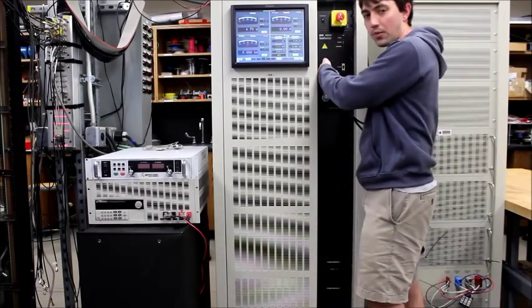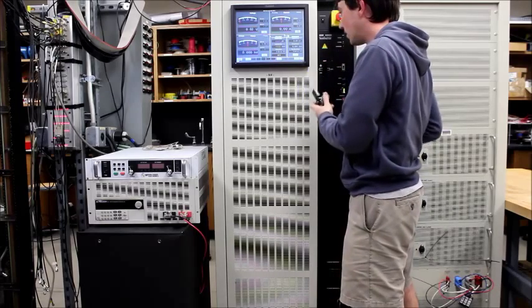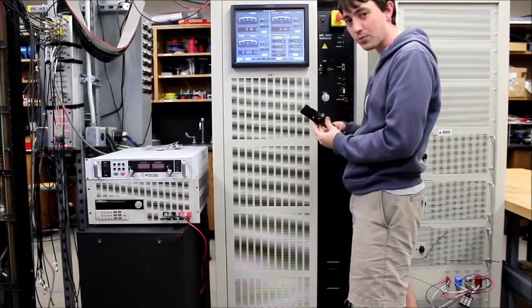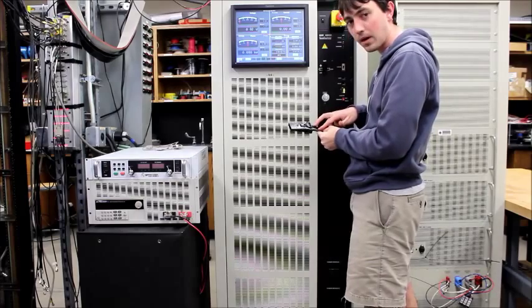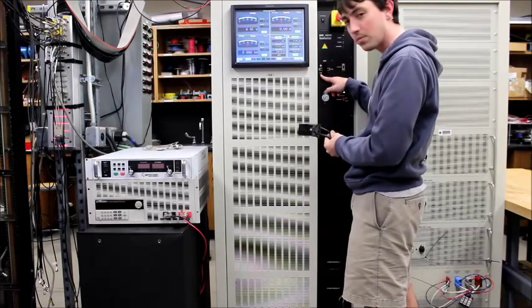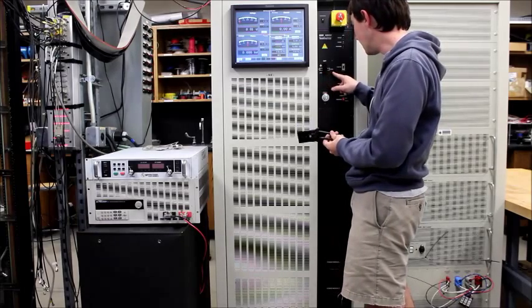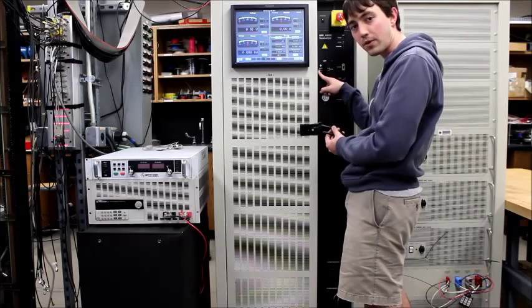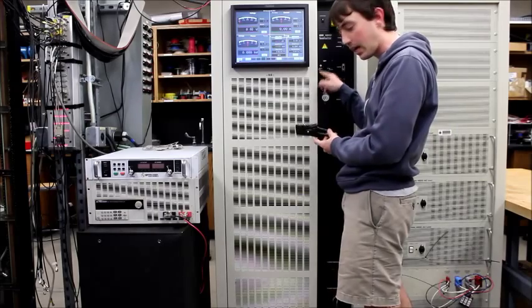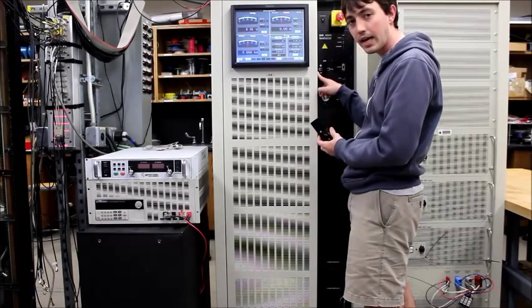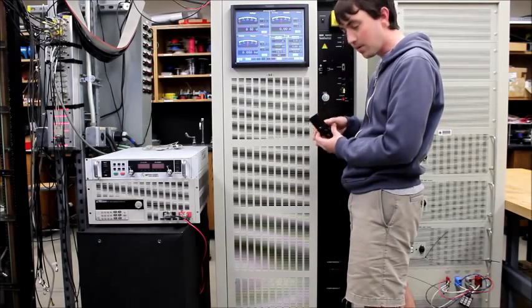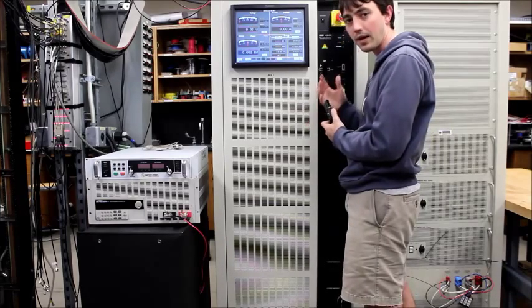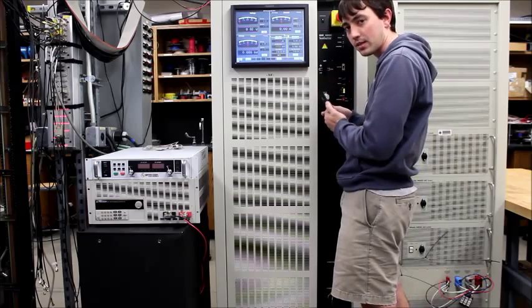So the first thing I want to show you is this plug. This is an Anderson Power Products plug, but it actually has three circuits in it. So there's the two main power circuits, plus and minus, the biggest plus and minus on the label. And then there's an EXT sense for external sense. And then there's another one for interlock, INT-LK. So the INT-LK is basically a jumper, and it's going to tell the unit that the plug is attached. That allows it to disconnect the output when the plug isn't attached.